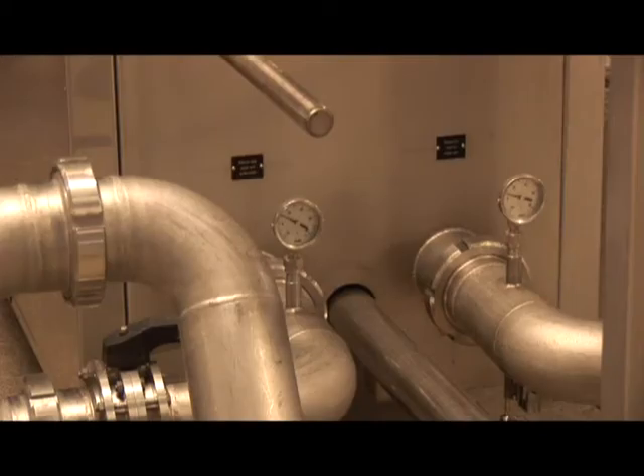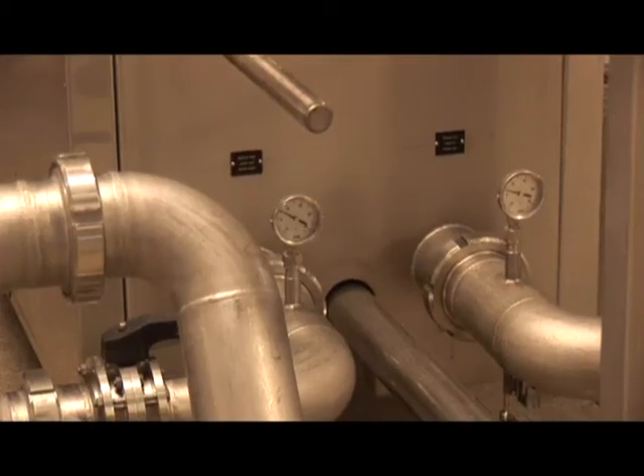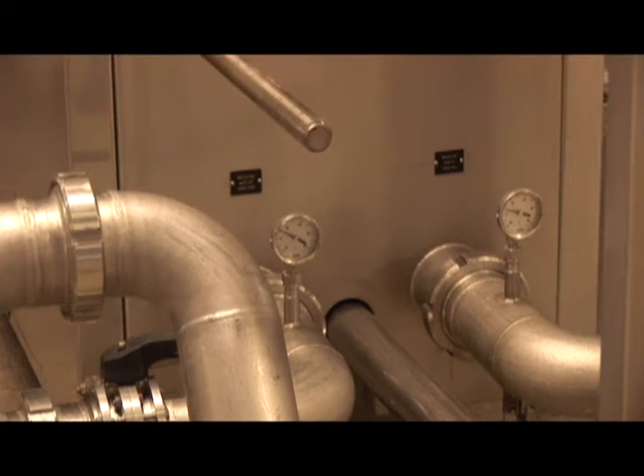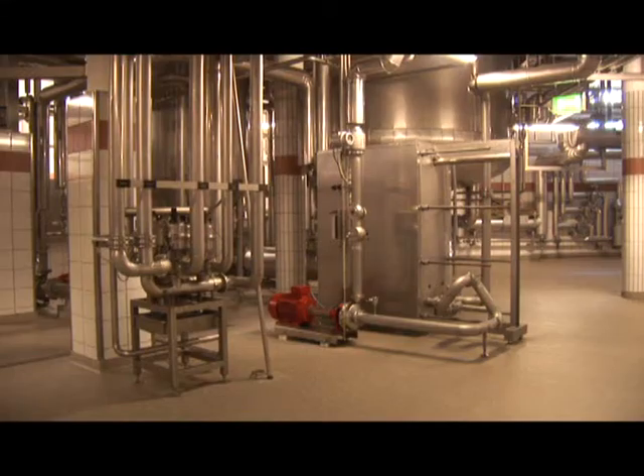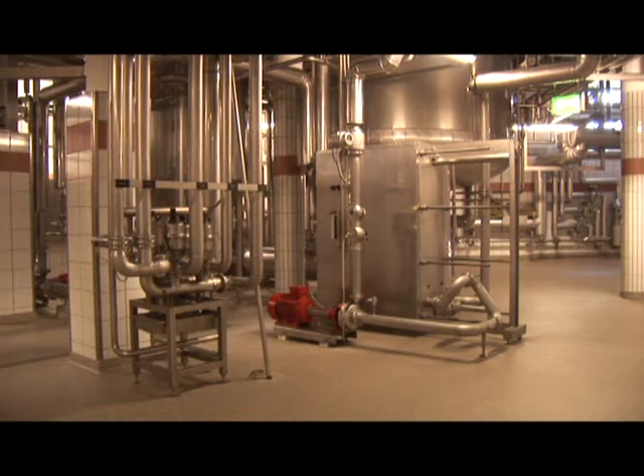An EMF, Promag H, and temperature regulation is shown. The pressure sensors make it possible to determine the formation of deposits, known as fouling. Two pressure gauges can be seen at the inlet and outlet. One can determine with the difference how far the fouling inside the heat exchanger has progressed and thus when it needs cleaning. The measurement can be easily automated.